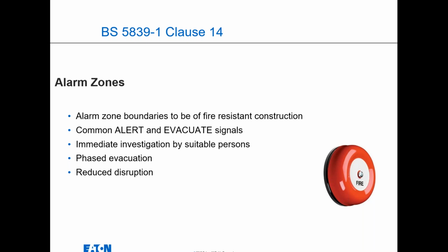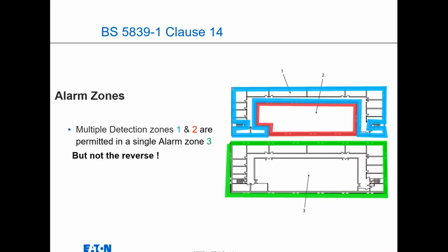You could also have phased evacuation if it's a large building and you don't want to tip out everybody at the same time, because you end up with bottlenecking in corridors and stairwells. So sometimes it's floor by floor. Within the space, you can have multiple detection zones in the same alarm zone, but not the reverse. Again, in a design situation, we would help you if you had that particular issue, and make sure we cover that when we do our designs for you, or our design intent.